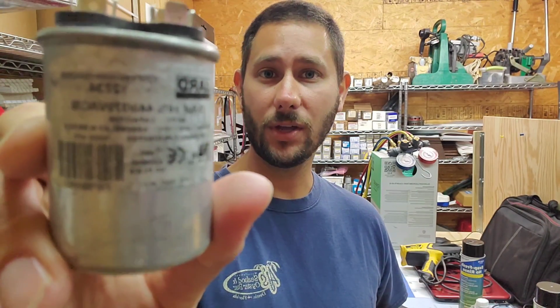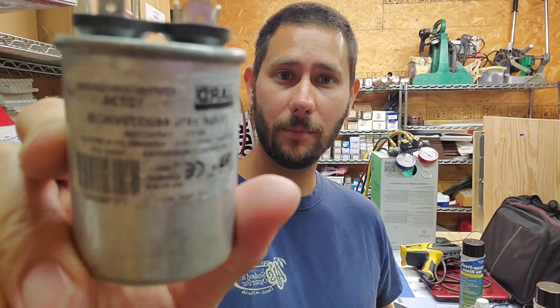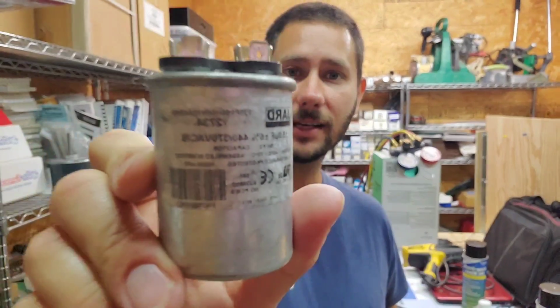in the long run. If you get a service and clean every year, or someone's performing maintenance on your equipment, they need to be checking the capacitor. They need to be checking the relay. They need to be checking the amp draw on the fan motor to make sure that the run load amps is proper, that the bearings are good. Evaporator fan motors, blower motors are common issues that can cause the air conditioning system to freeze.